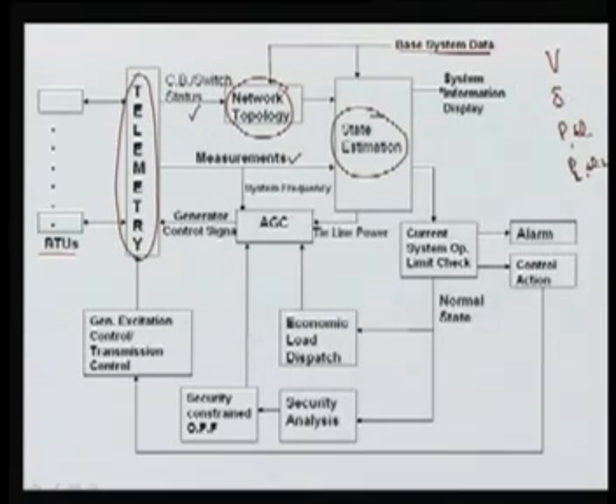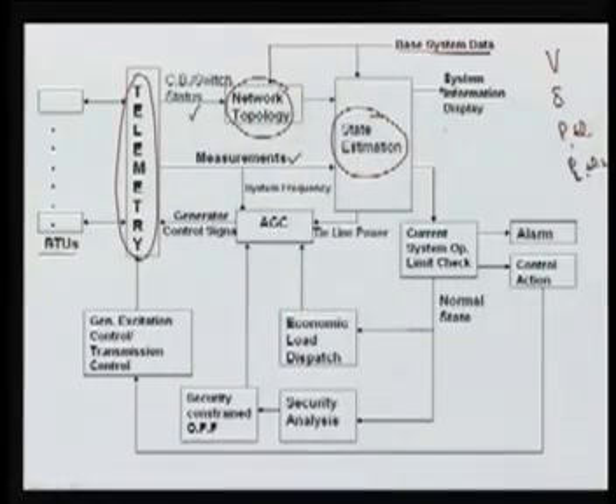We also determine the voltage and angle in power flow analysis, but there we normally solve the power balance equations and get the voltage and angle as the solution. However, in state estimation the number of equations is large, whereas in the load flow the number of equations is equal to the number of unknowns, so we get a unique solution at a particular condition. In state estimation, since we are measuring the data from the RTUs and it comes through the communication channels, that is, through the telemetry information, we assume these measurements will have some errors and noise.